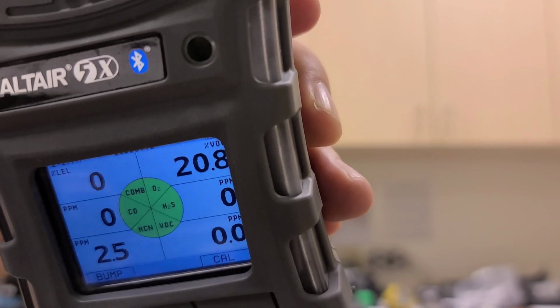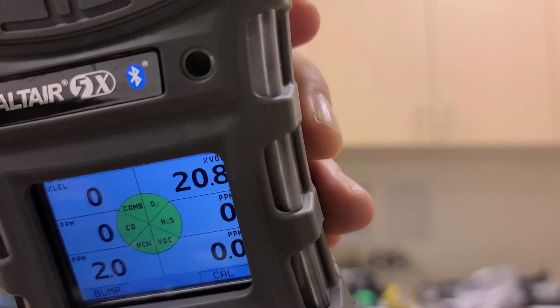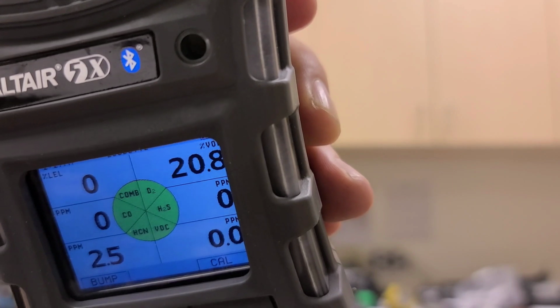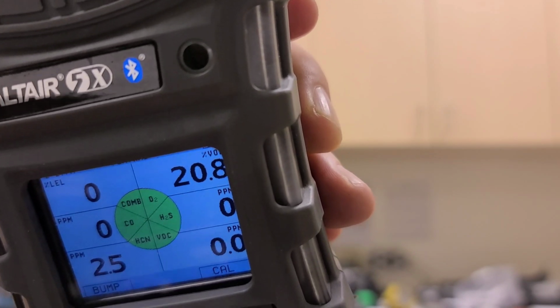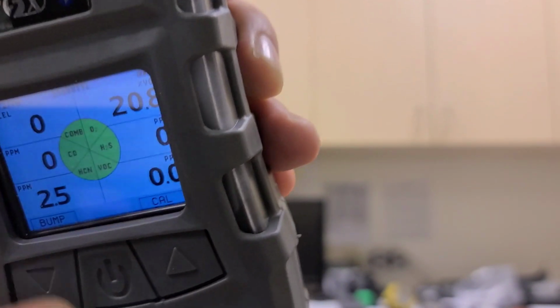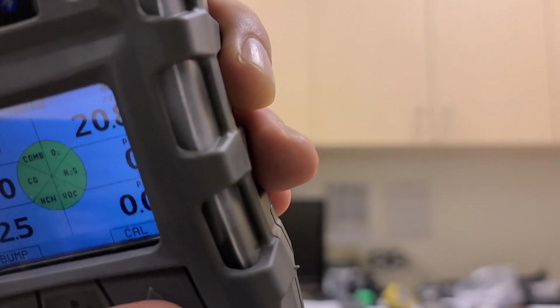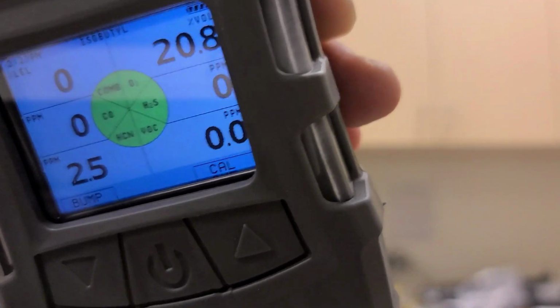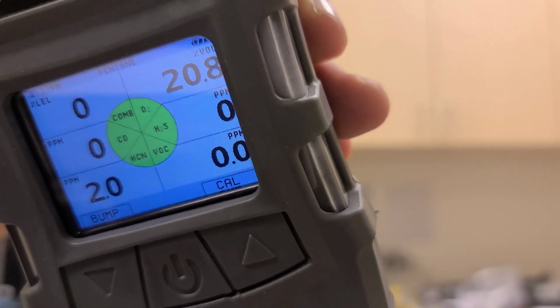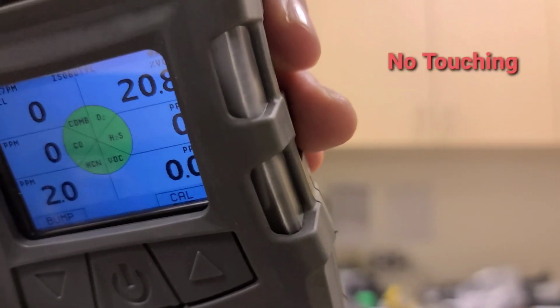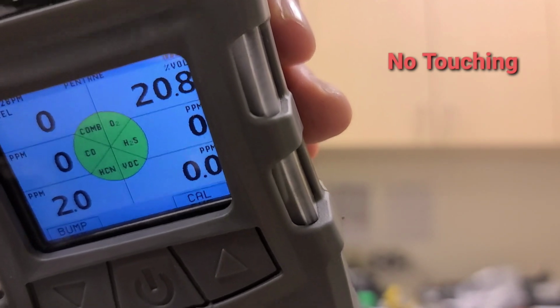So it's measuring right now. It's got green in the circle for each sensor. When you're getting close to your alarms, that'll go red. The bottom button, as you saw, shows bump. Right shows cal. These are the buttons I had mentioned I don't want you to touch because you need to have gases to operate in those menu options.